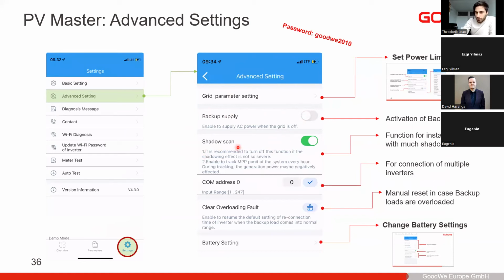Here we also have a shadow scan. This is for when you have thick shadows covering larger parts of your PV modules - you can tick this box and it will scan for the global maximum of the MPPT. This could increase the yield if you have very sharp shadows on your modules, but if you don't have that, and it's only from clouds or similar, I recommend not using this to optimize the yield.